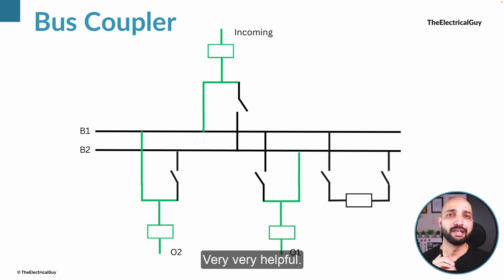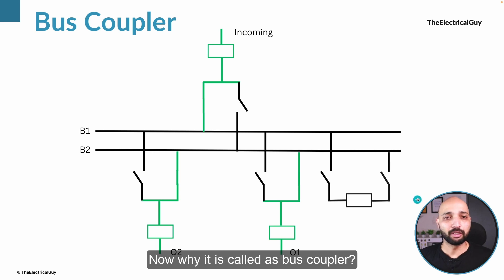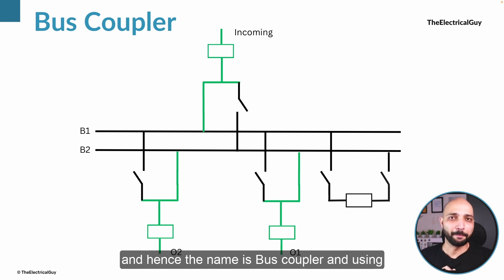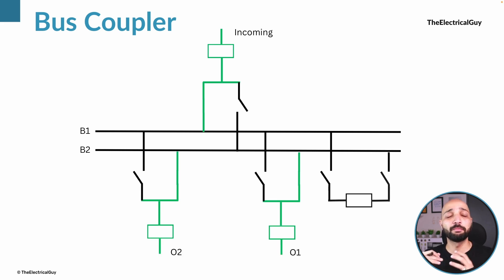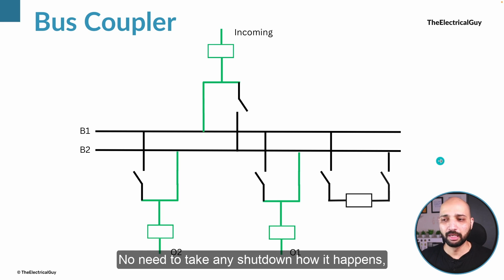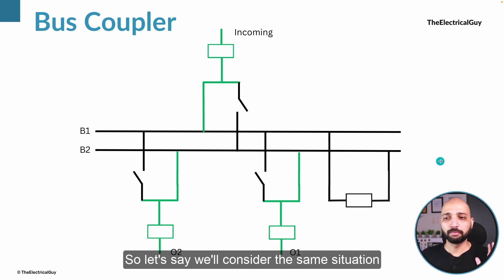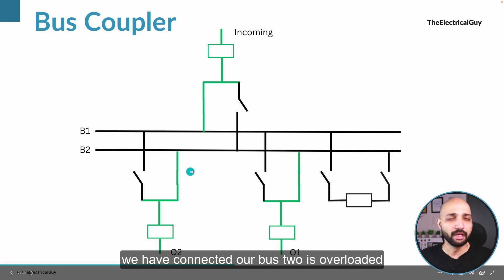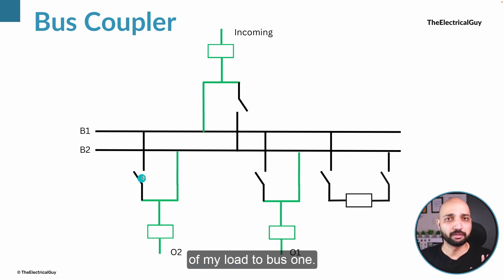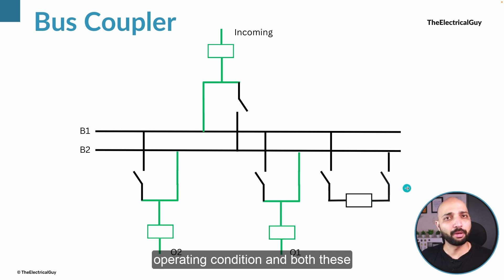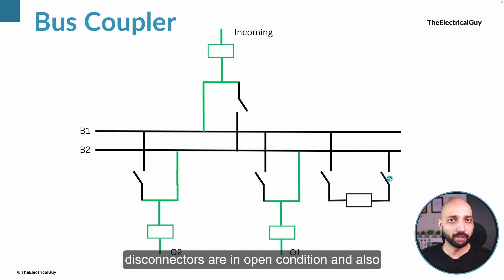Now let's get back to the bus coupler. As the name suggests, it couples the two buses — hence the name bus coupler. Using this we can transfer load from one bus to another in live condition with no need to take any shutdown. Let's consider the same situation: bus two is overloaded and I want to transfer some load to bus one. In normal operating condition, both disconnectors of the bus coupler and the circuit breaker are in the open condition.